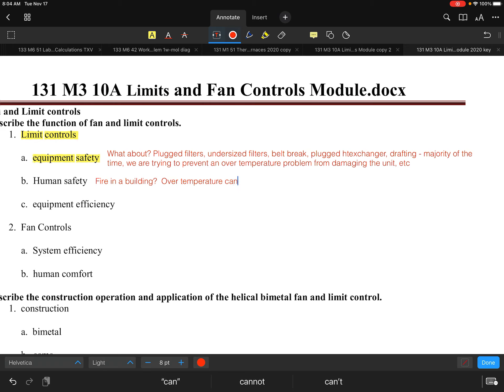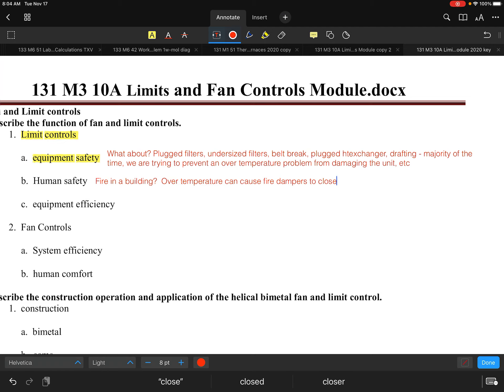Another human safety concern is over-temperature in duct systems — especially on commercial rooftop applications that have fire dampers with fusible links. If the air temperature going down the duct system is too high, it causes these fire dampers to close, blocking the airflow. The intent is to prevent the unit from feeding oxygen and air to a fire.